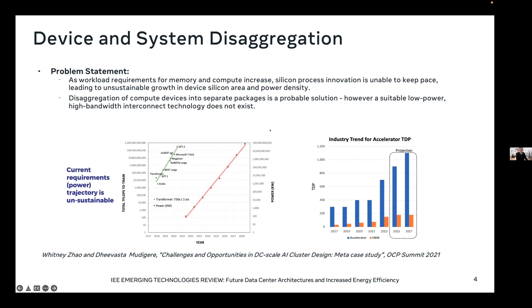This scales very quickly to many, many megawatts. You can also see on the right-hand side the corresponding industry trend for some of the actual device accelerators. We're all trying to push off introducing things like liquid cooling as far as possible because of the cumbersomeness of trying to upgrade data centers with that kind of infrastructure. But you can see that very quickly by 2025 and 2027, you're getting to total power dissipations that will probably require that. The challenge for us as an optical community is that one way of solving this problem is to disaggregate these multi-chip packages into separate devices in order to spread out the power densities, but we don't have a suitable high bandwidth, low power interconnect to facilitate that.